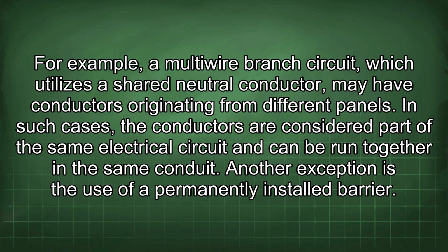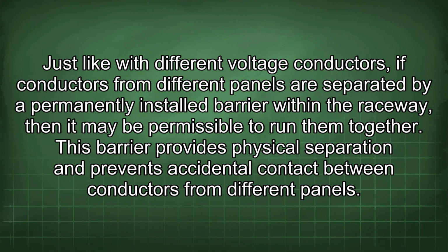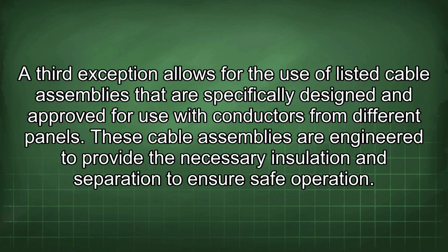same conduit. Another exception is the use of a permanently installed barrier. Just like with different voltage conductors, if conductors from different panels are separated by a permanently installed barrier within the raceway, then it may be permissible to run them together. This barrier provides physical separation and prevents accidental contact between conductors from different panels. A third exception allows for the use of listed cable assemblies that are specifically designed and approved for use with conductors from different panels. These cable assemblies are engineered to provide the necessary insulation and separation to ensure safe operation.